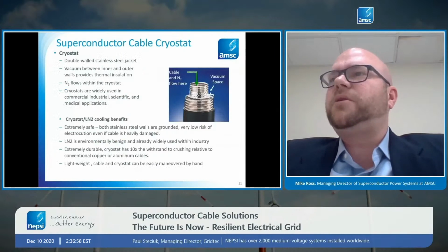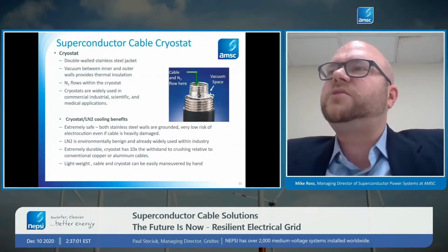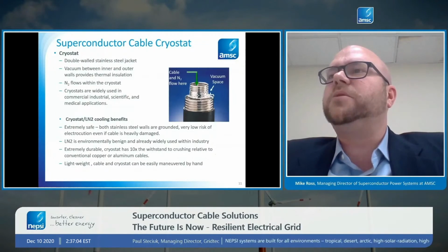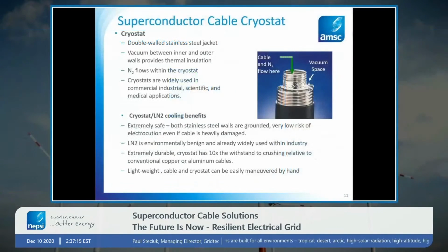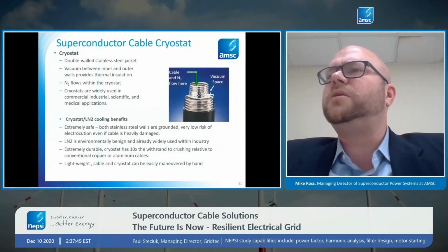So we talked a little bit about cryostats and what that is. And again, cryostats are a technology that's much larger than superconductor cables. So the industry buys a lot of what they call vacuum jacketed pipes from various manufacturers to move very hot or very cold liquids and gases around factories and other applications. So this is a technology that's been around about 40 years, available from many suppliers. And we take that existing, very mature technology and put our cable inside that. The cryostats are flexible. They're corrugated, as you can see, so you can bend them, and they fit on standard utility cable reels with no problem whatsoever.